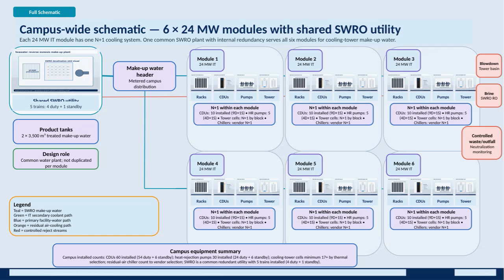Here we have a full schematic overview of the Batum Coastal Data Center's water supply and cooling system, focusing on the integration of SWRO desalination, direct liquid cooling, and cooling towers. The campus consists of 6 modules, each delivering 24 megawatts of IT capacity. Each of these modules is equipped with its own N+1 cooling system to ensure reliability.